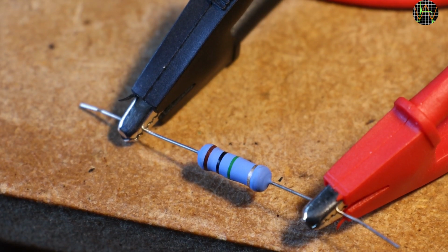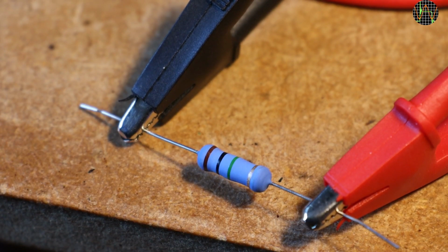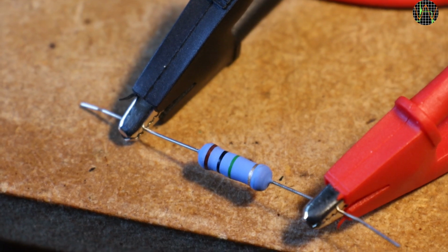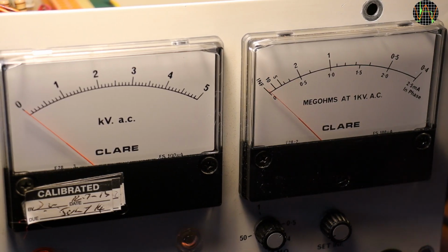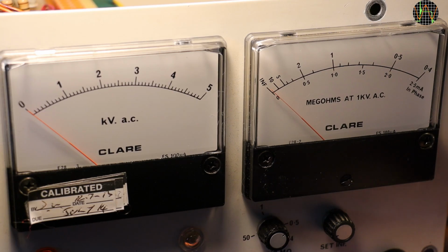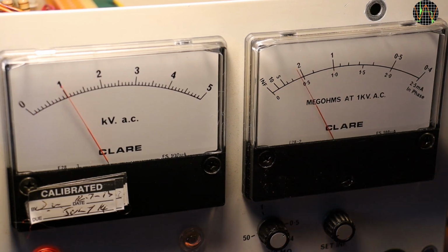Therefore I put a 1 megohm resistor on the output. With 1 kilovolt I should see exactly 1 milliamp or 1 megohm on the scale. I can't do this too long though, because 1000 volts and 1 milliamp means the resistor is loaded with 1 watt. I'm not sure if this resistor is rated for 1 watt or 2 watts, but let's assume the worst. Running the test clearly shows the miscalibration. Instead of 1 megohm, the meter shows over 2 megohms.